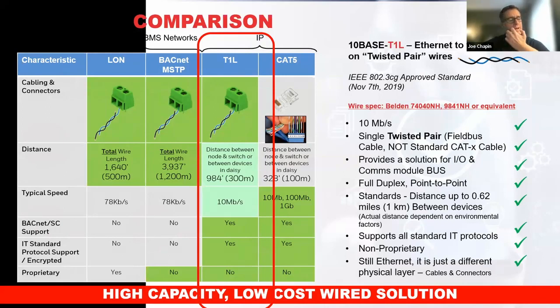We have a T1L adapter. If I have a very long run up to a kilometer, I can go and put that in and achieve more than 300 meters. I can almost basically triple my distance without having a controller. And again, 300 meters in a building is a long way to go. But for those times that you don't have that, you have this ability. So again, remember T1L, remember reuse existing wiring, remember not placing new cabling, and remember we've got the controllers that can do that, several controllers for that matter.